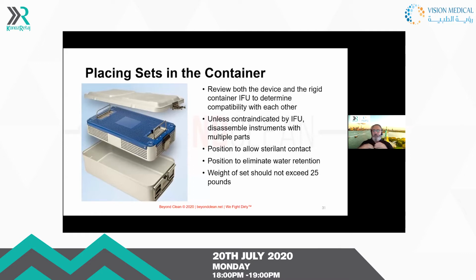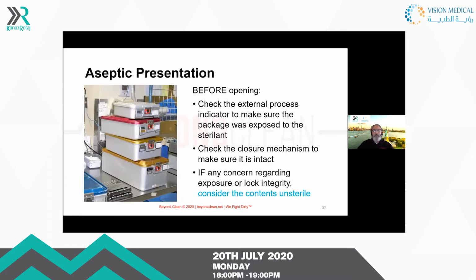You want to review their IFU, position the instrument set so it will allow the sterilant into the container, eliminate water retention, and again, you should never exceed 25 pounds. Again, you're going to check for those external markers to make sure that they have changed after sterilization so that you're using a safe product for your patients.